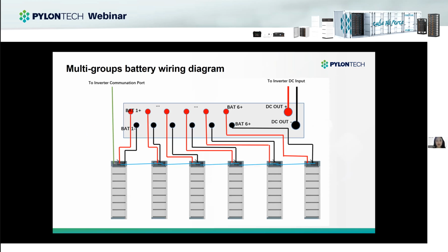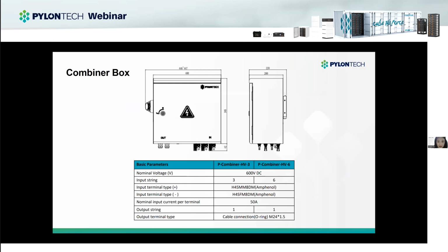If you want to add capacity, you could connect the BMS in parallel. Between the BMS, you should connect the link one of the master battery to the second link 0 port, and the master battery CAN port would connect to the inverter. And also we need a combiner box to store the power cable. We also provide this combiner box.